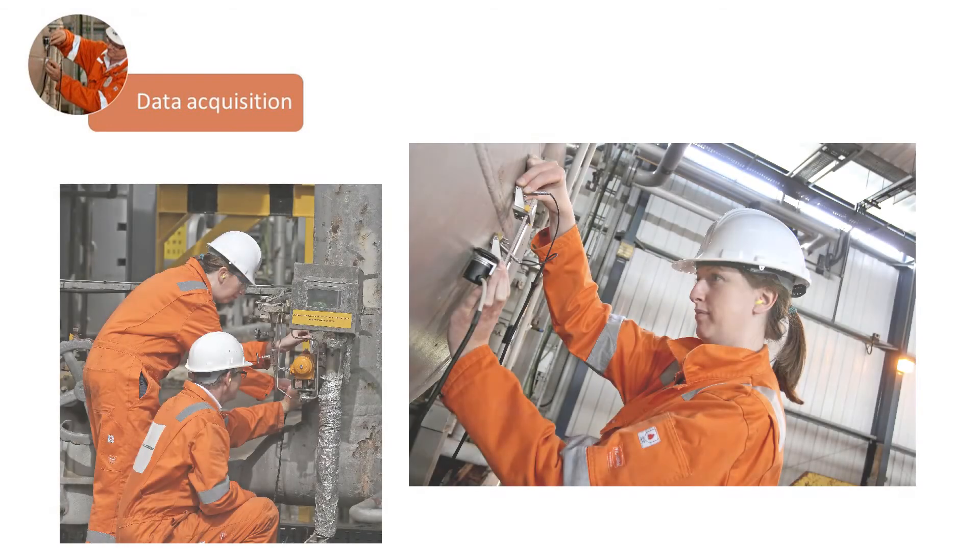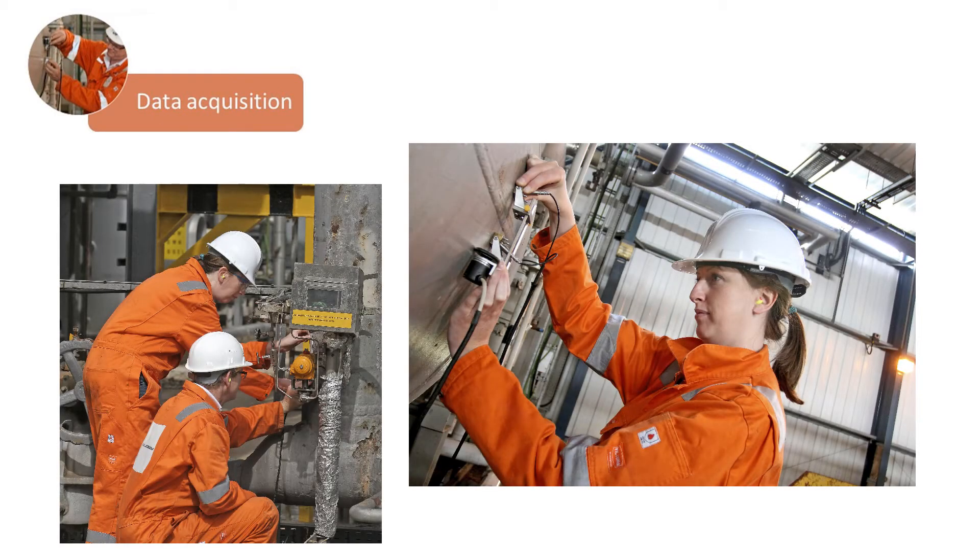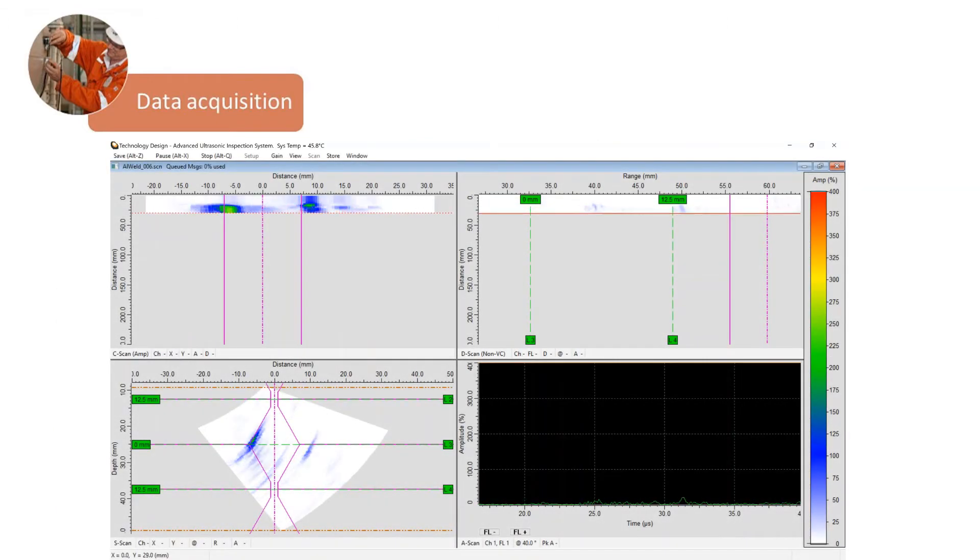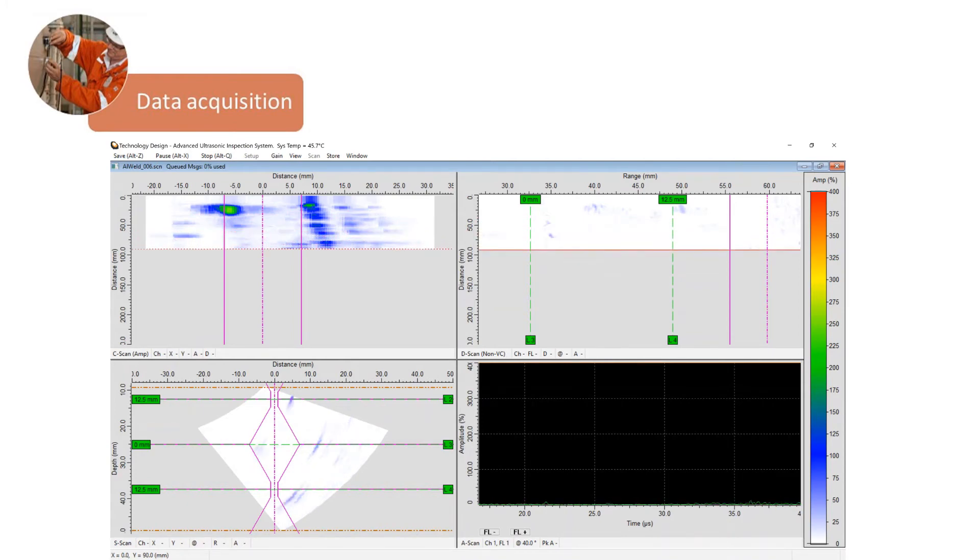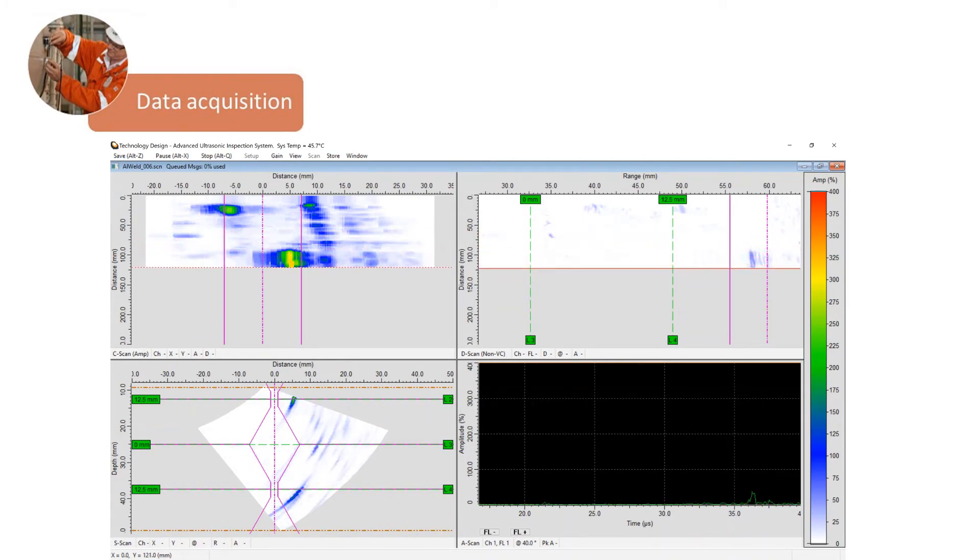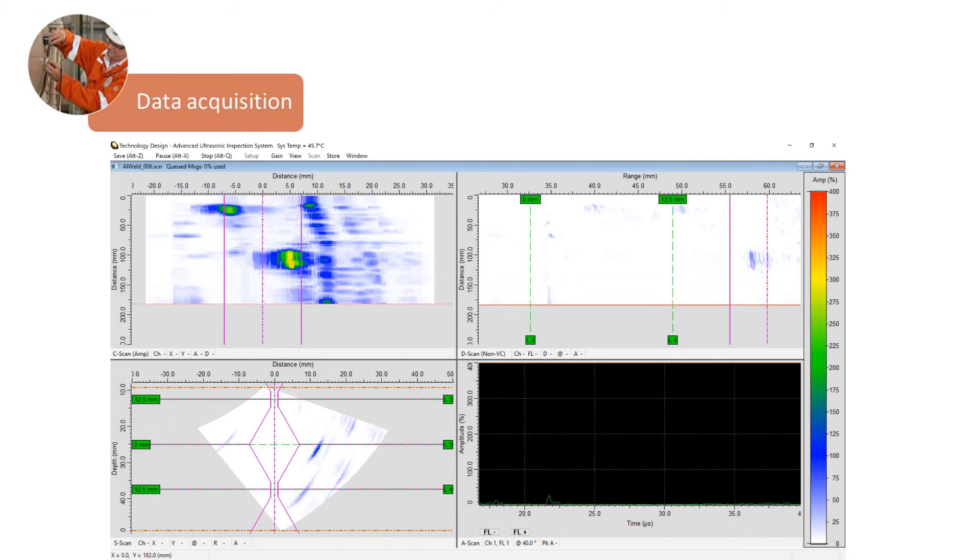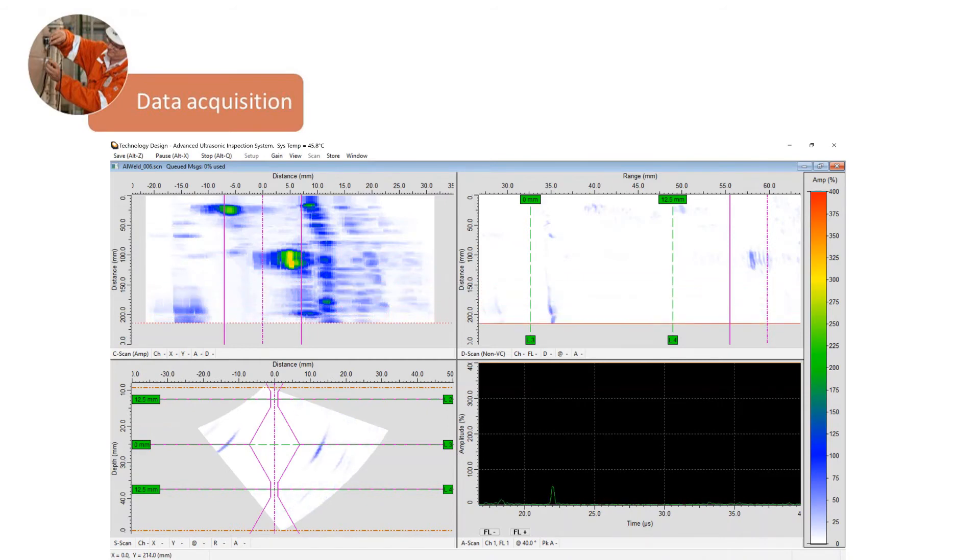Data Acquisition is the work done at the inspection phase to gather and store the inspection data. It may involve any one of or combination of several scanning procedures, testing using the A, B, C, D, and S scan techniques or zonal discrimination, applied manually or using motorized scanners for common examples.